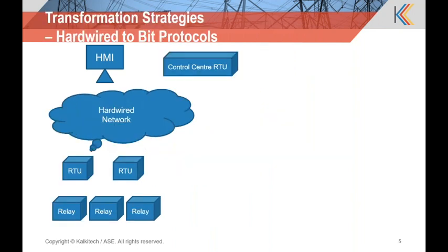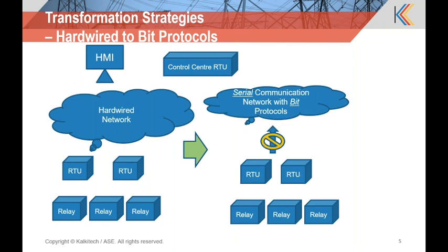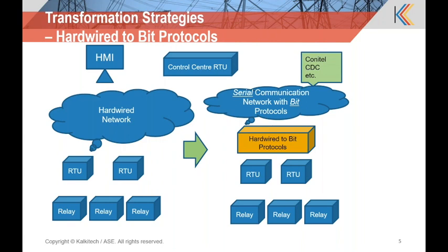Let's talk about our hardwired-to-bit-protocol use case. In this scenario, we have a hardwired network solution with a dedicated I/O port interface which retrieves and collects information and sends it to the control center. There's a need for a bit protocol to be communicated upstream across existing communication segments. That's where we fit in, because we provide support for legacy and standard protocols across our products, including but not limited to Conitel, CDC, Harris, etc., to name a few.